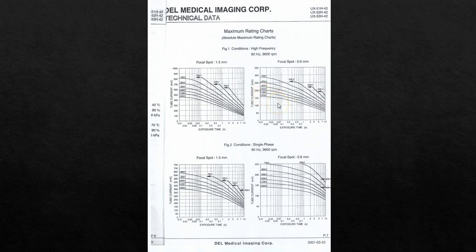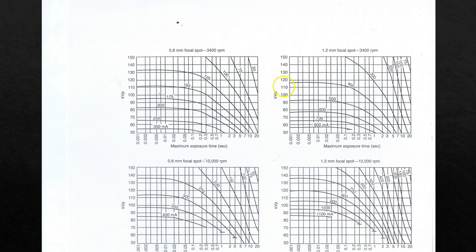Again, that's fine — we don't typically use 100 KVP for extremities anyway. We're going to probably be using about 70 KVP. And as you can see at 70 KVP, I'm allowed to go up to almost 300 MA on a short exposure time. The curve isn't all that steep, so I can have about a 1/10th of a second exposure time at 300 MA.